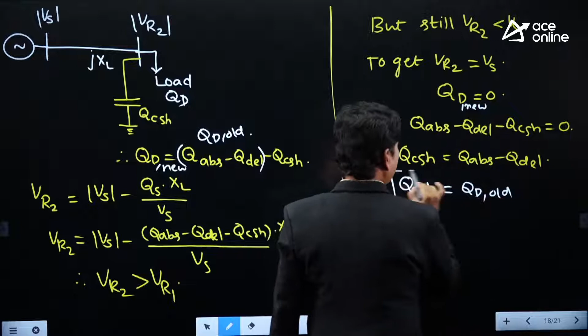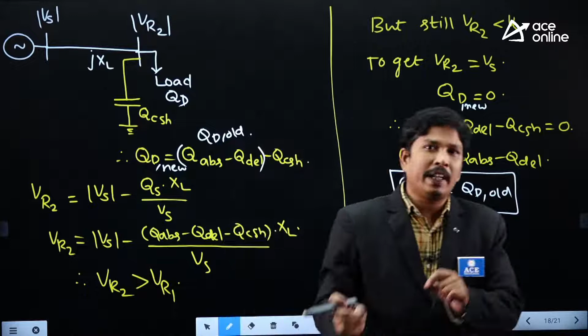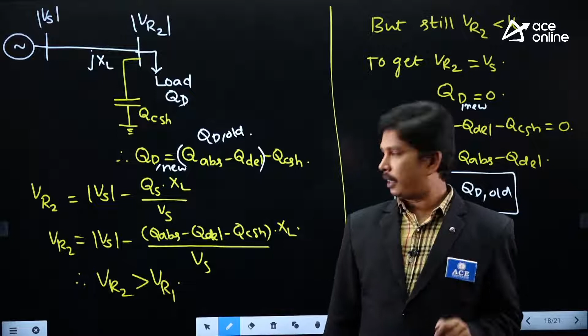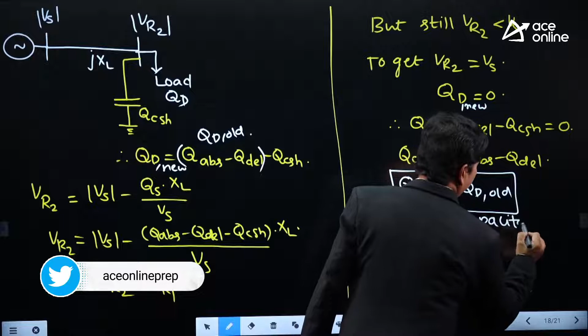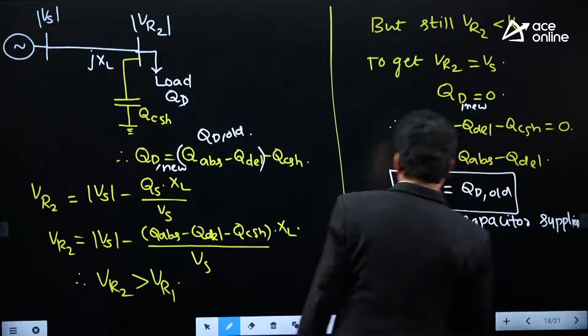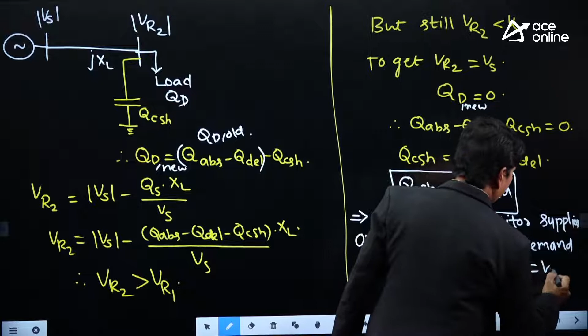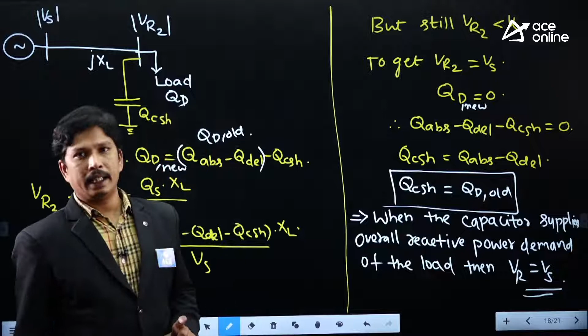That means the capacitor has to supply the overall reactive power demand of the load. Only when it is able to supply the overall reactive power demand of the load is it possible to get the receiving end voltage exactly equivalent to the sending end voltage. So that is the conclusion we can write. When the capacitor supplies the overall reactive power demand of the load, then VR is equivalent to Vs. So we can get the receiving end voltage exactly equivalent to the sending end voltage.